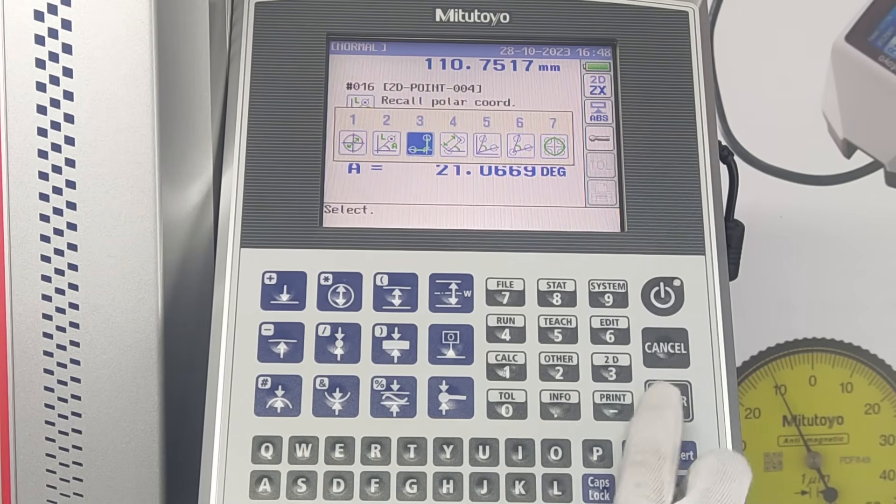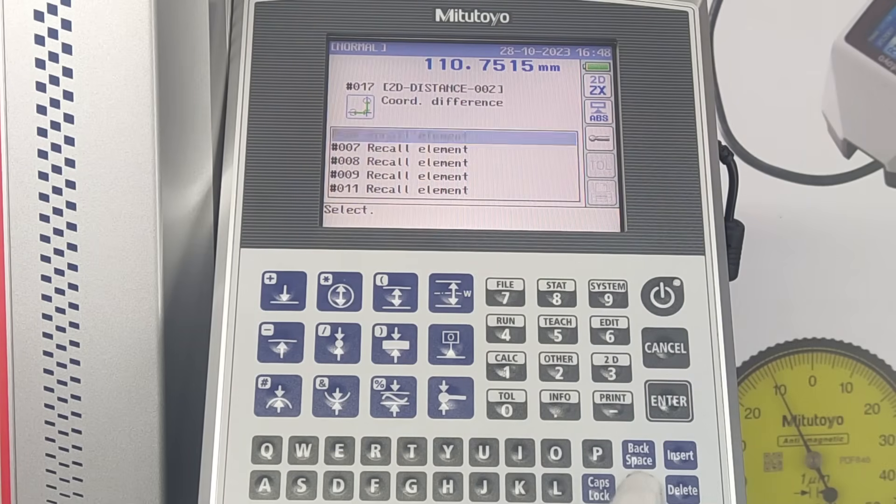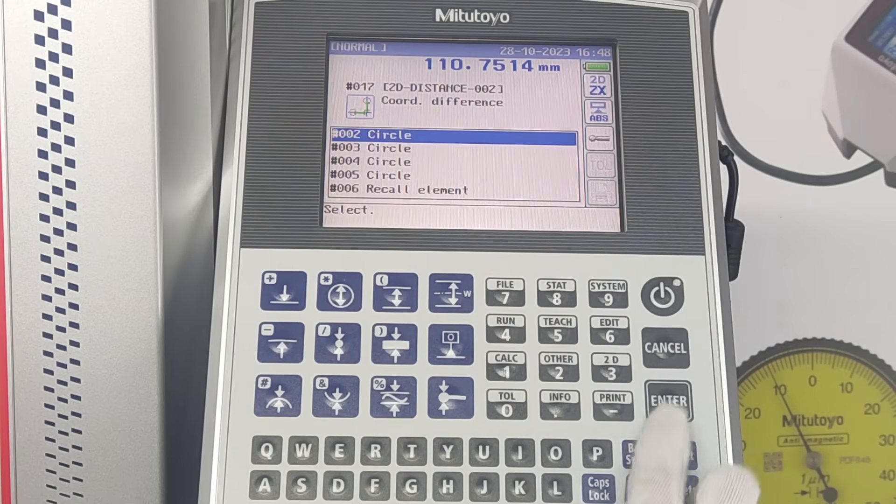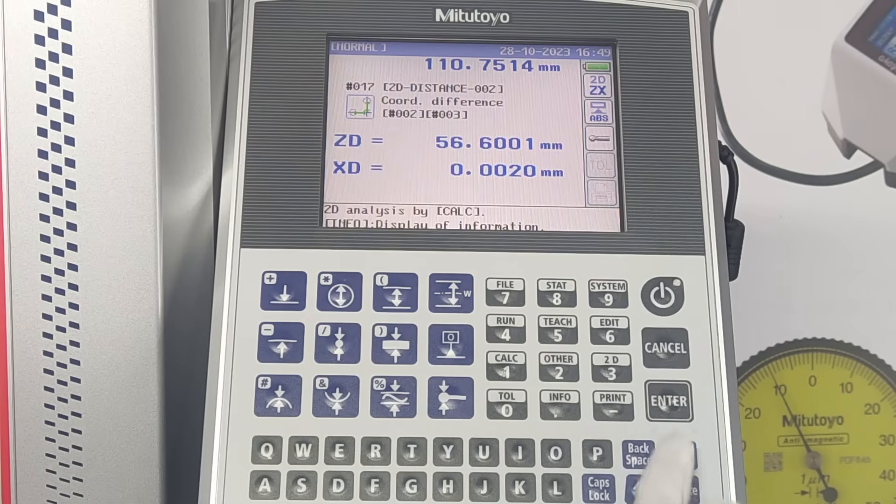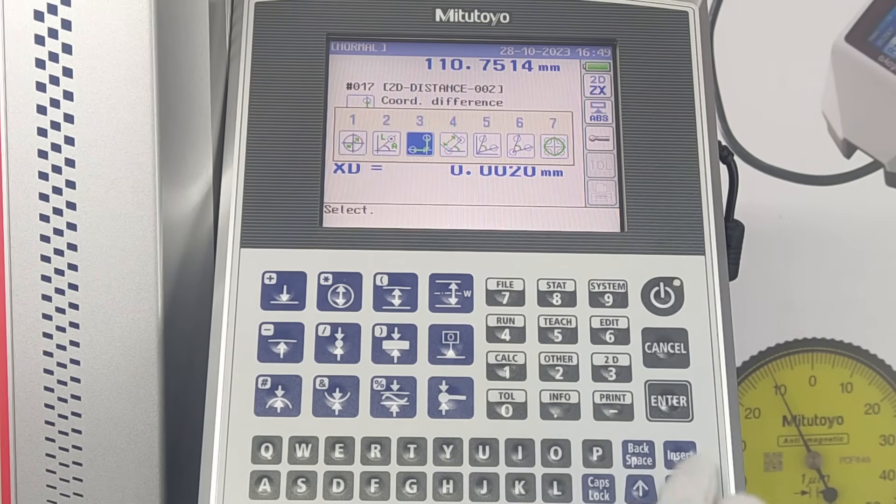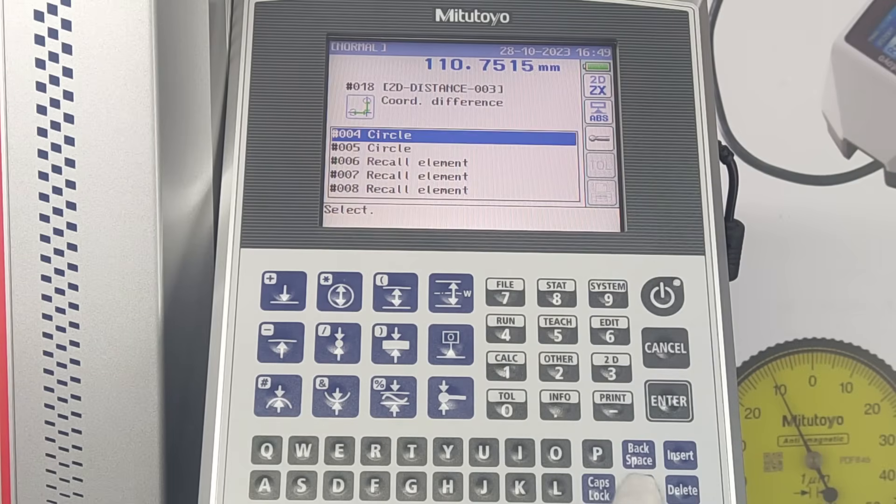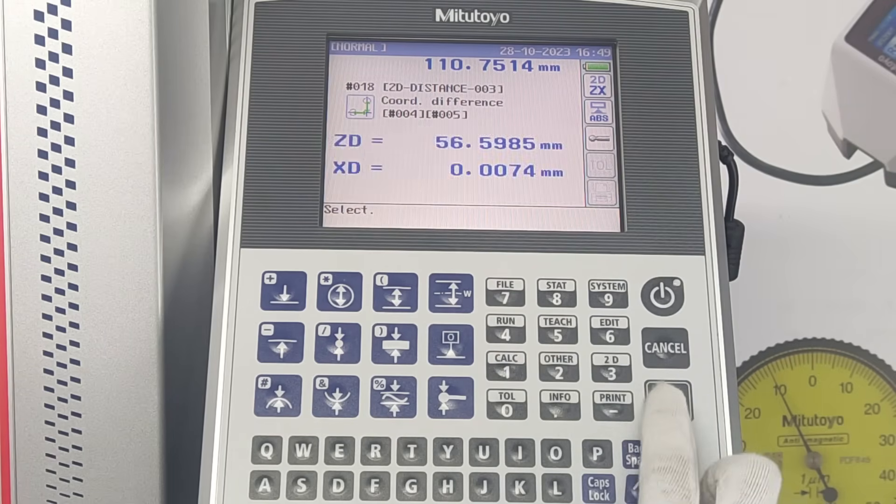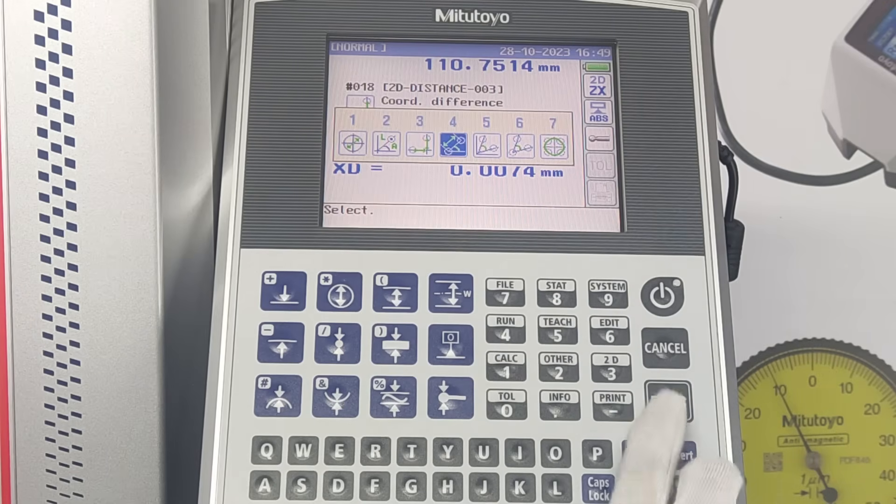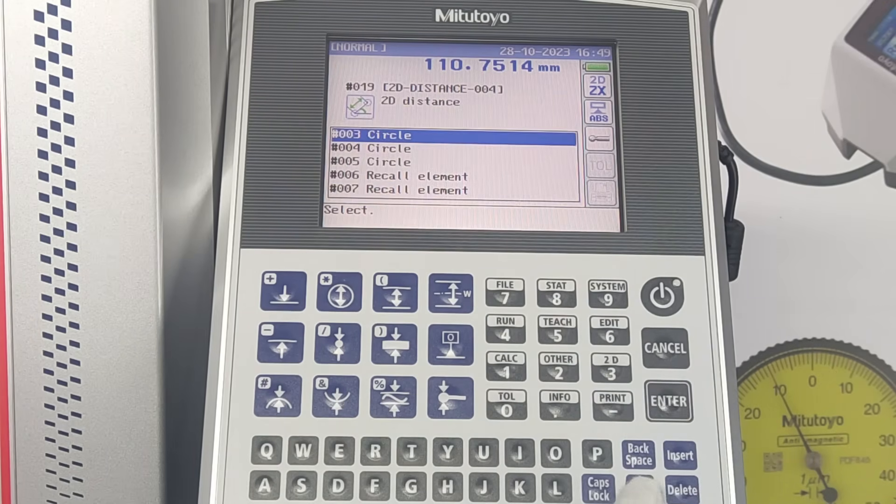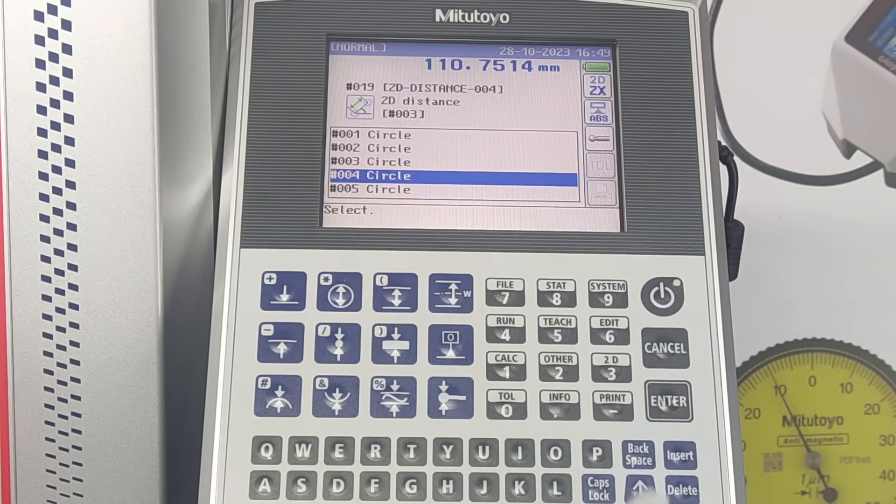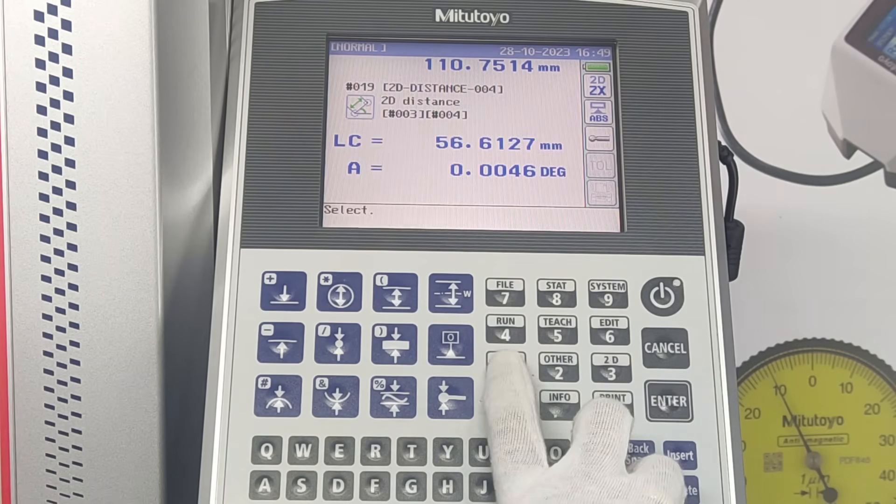The third option is to view coordinate distance. This function loads two measured elements that consist of 2D data and determines coordinate difference between X axis and Z axis, XD and ZD. The fourth option is to view distance and angle between two circles. Select any two circles. LC is the distance and A is the angle.